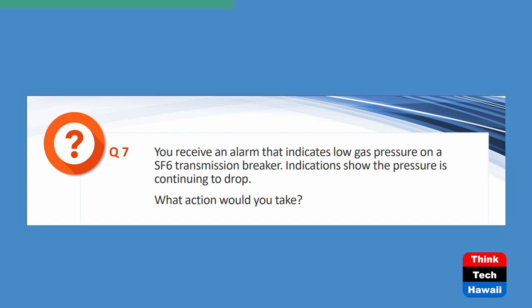The next question here is, you receive an alarm that indicates low gas pressure on an SF6, which is sulfur hexafluoride, transmission breaker. Indications show the pressure is continuing to drop. What action would you take? Now, before we go any further, let me explain why it's important. So sulfur hexafluoride has the ability to break the arc whenever a breaker opens up, and that's used to extinguish the arc across the contacts.